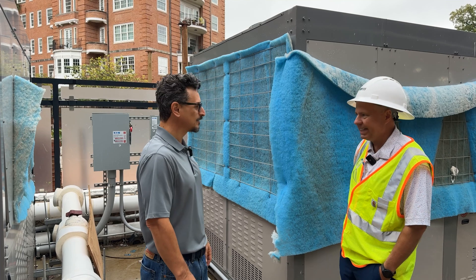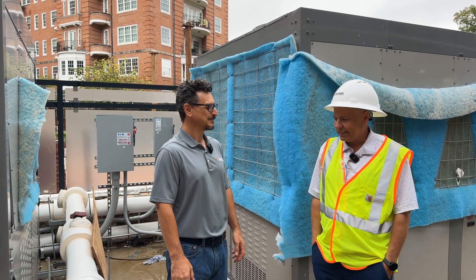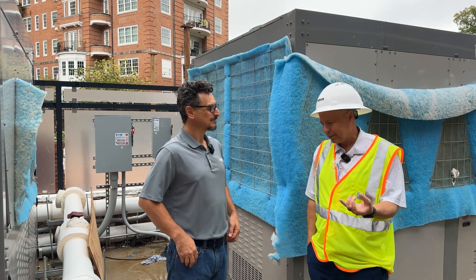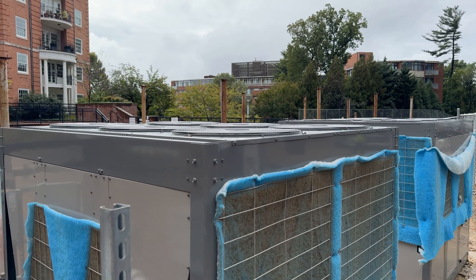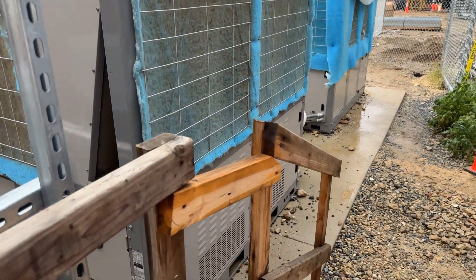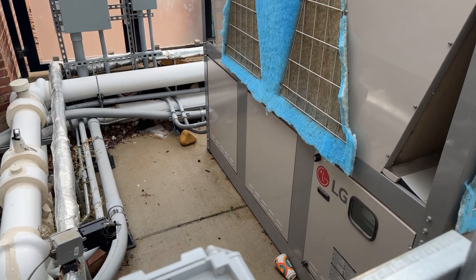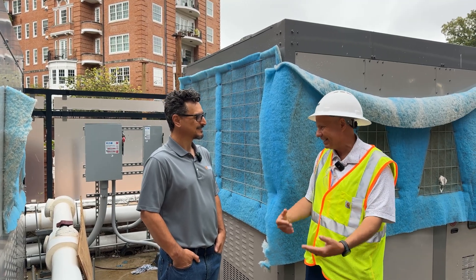So they needed cooling and heating — that's an important point. With one machine they got both heating and cooling. They wanted a temporary solution. They had existing two-pipe hydronic fan coils throughout the space, so it made a lot of sense. They don't need simultaneous heating and cooling — just one or the other.